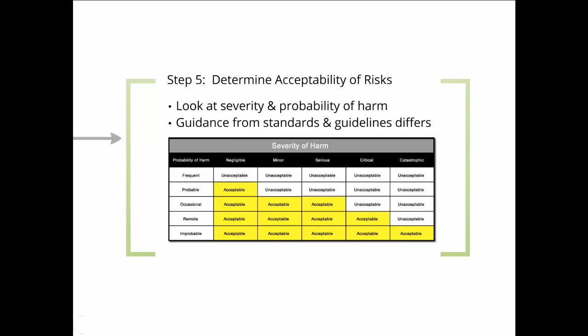CLSI's Risk Acceptability Matrix is but one example and one way for creating the chart. Ultimately, it will be up to the team to determine whether a given risk is acceptable or not. Sometimes the judgment can be a difficult one. For example, if a given failure is occasional and the severity of the harm is serious.